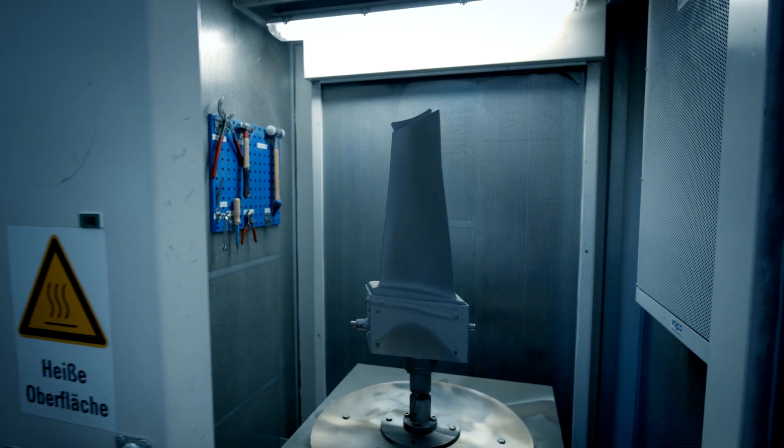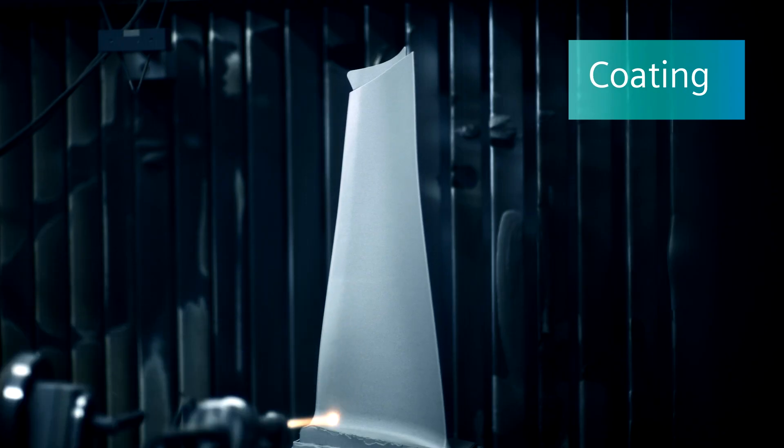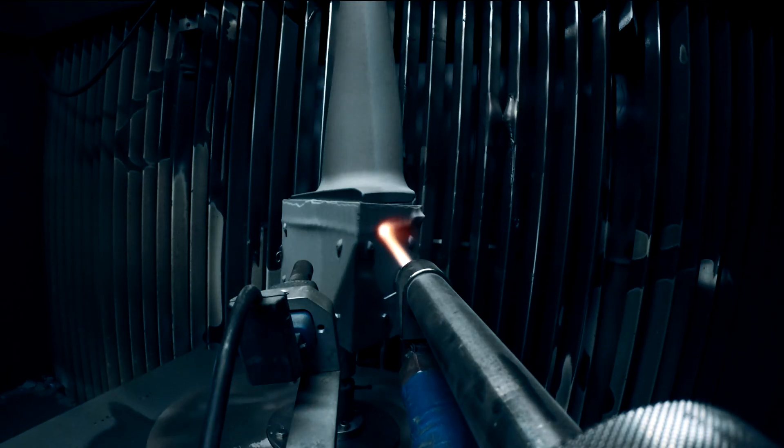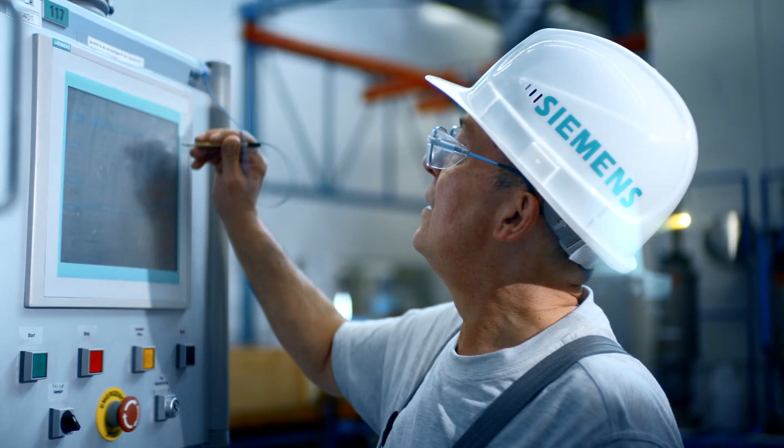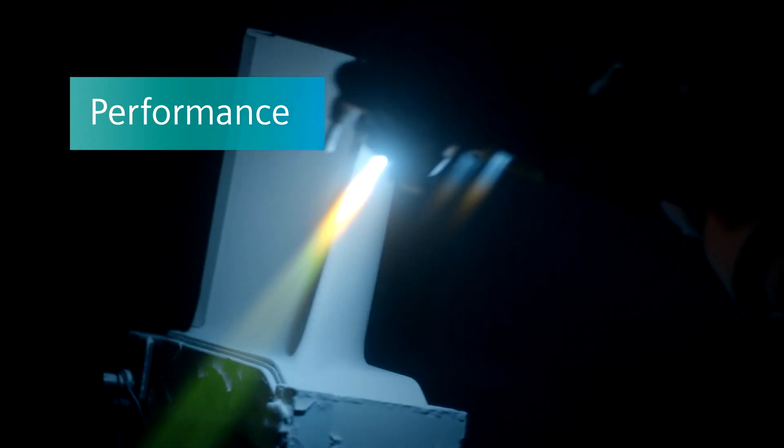All blades and vanes receive C-coat state-of-the-art coatings using appropriately optimized spray or vapor deposition techniques. Improved oxidation resistance and enhanced thermocycling performance give them today's optimal component protection.